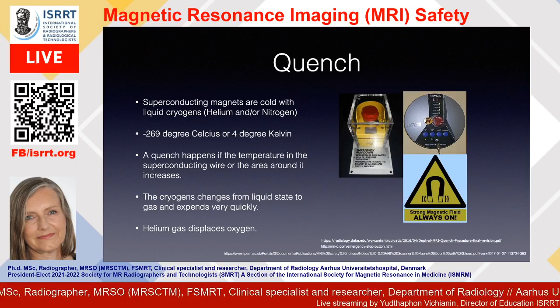And a quench happens if the temperature in the superconducting wire or the area around it increases. That causes the cryogens to boil off, so they change the state from liquid state to gas, and that makes them expand very quickly. Helium can expand up to 750 times, and helium gas also displaces oxygen, and that is part of the reason why we have to evacuate the room immediately when a quench happens.